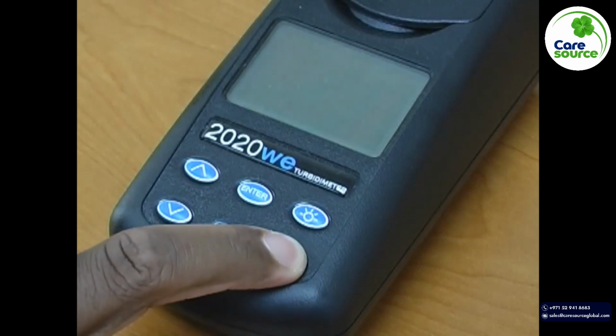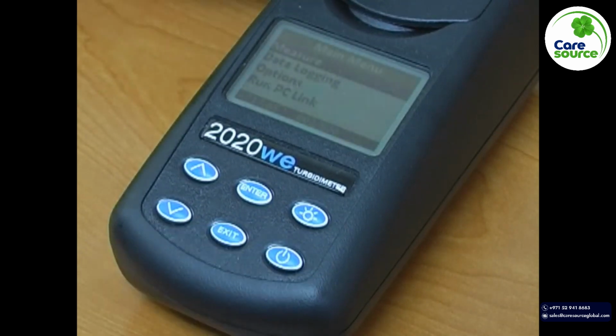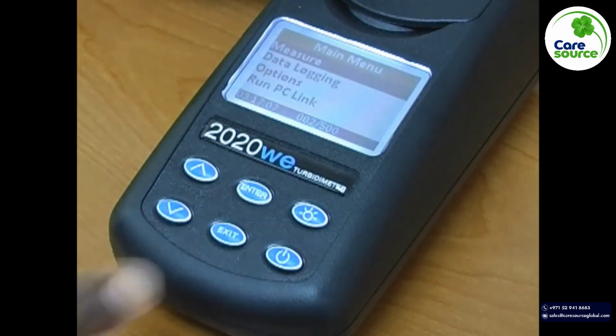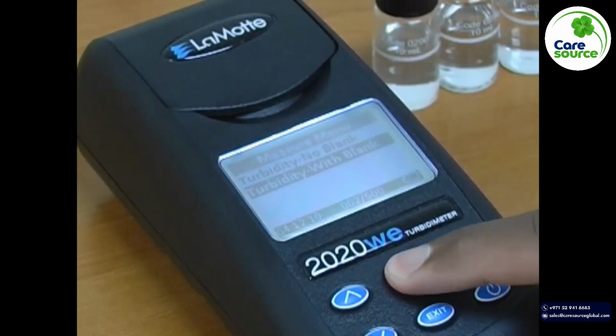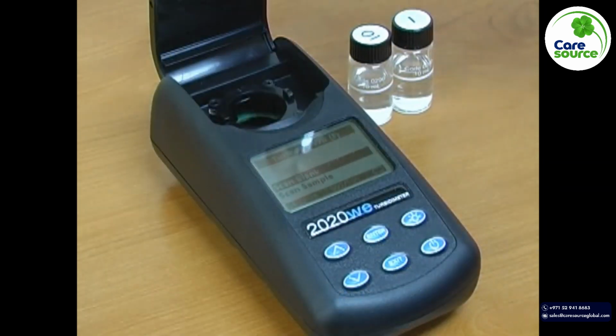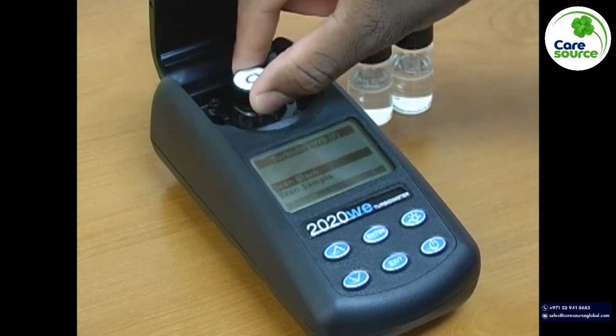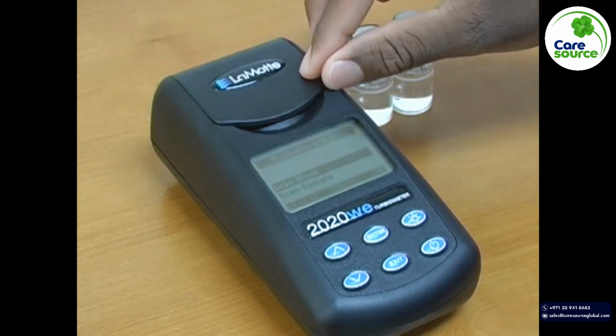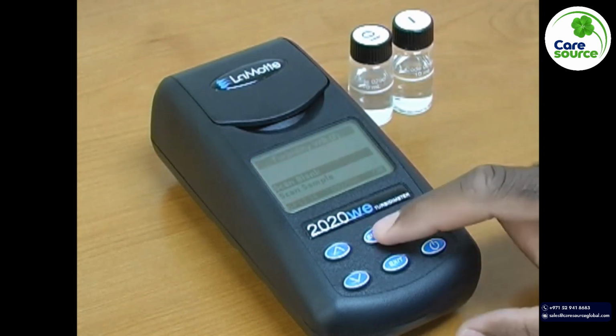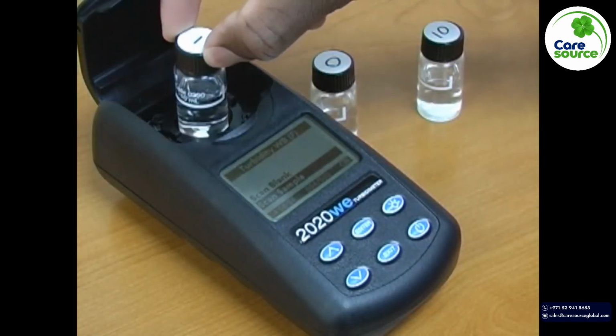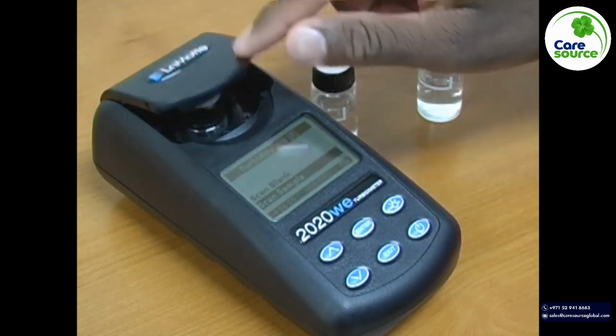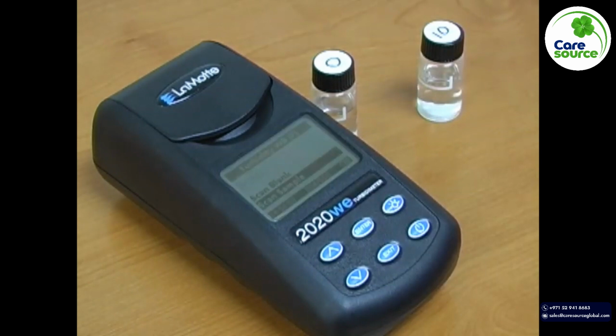Press the power button to turn the meter on. Select Measure. Select Turbidity blank. Insert blank, making sure to align the indicator arrows with the line on the tube. Close lid. Press Enter. Remove blank and place the 1 NTU standard into the chamber and press Enter to scan sample.